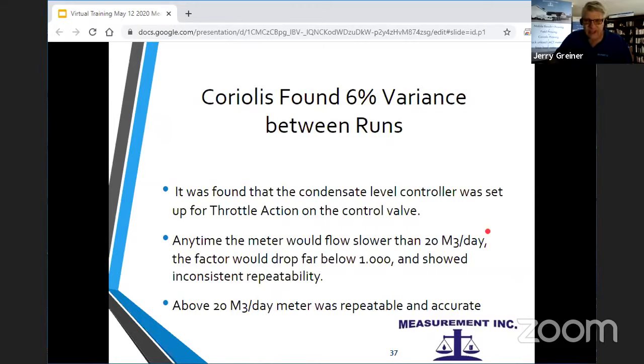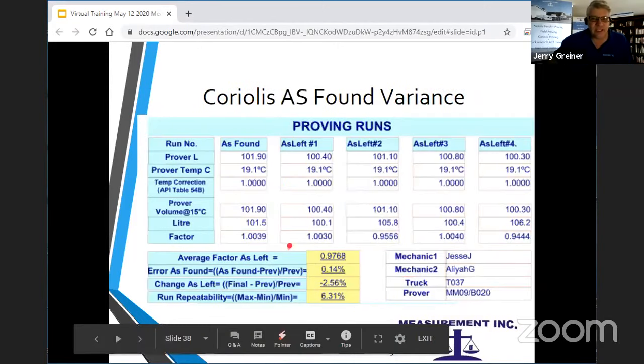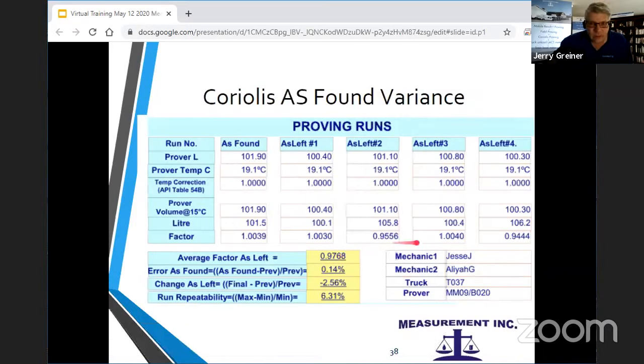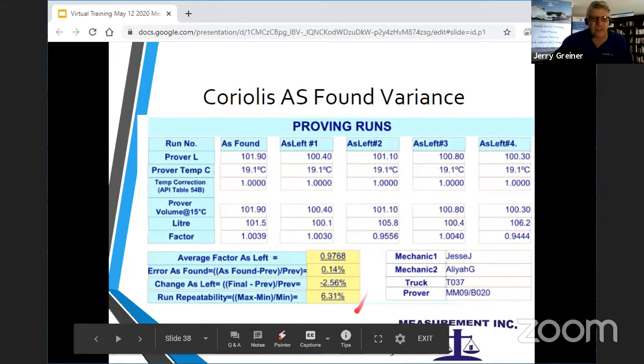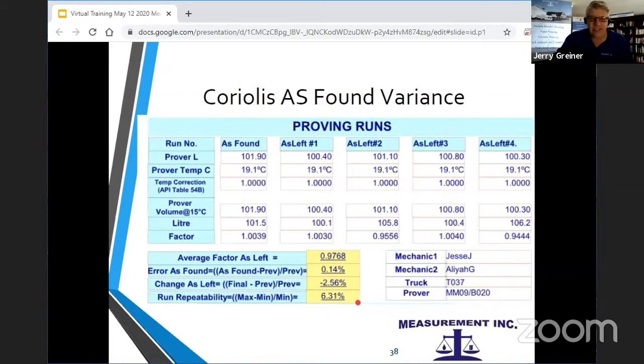The well made like in the range of 60 cubes a day, so a lot of the time it was above that, but it would come in slugs. So a lot of the time it would be accurate, and then some of the times very inaccurate. Here's a proof that we did, and you can see the numbers. The meter factor went from about 1.003 to 0.94. It's about 6% between runs, and it was directly related to the flow rate we found. That was one of those duh moments that you sometimes have.